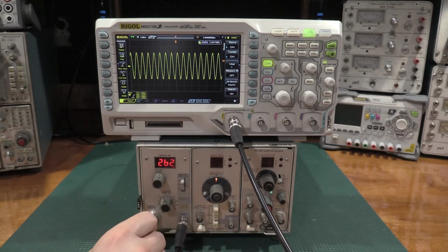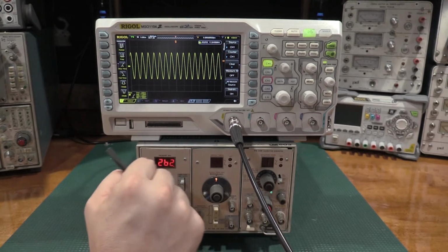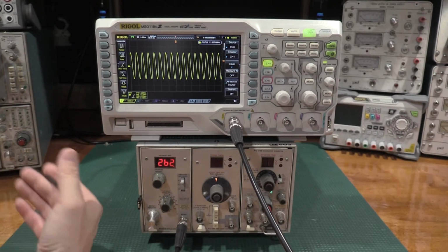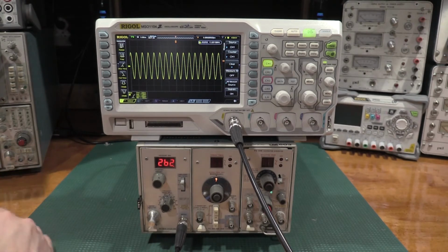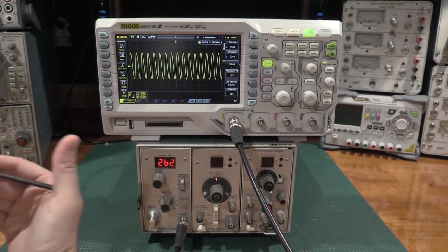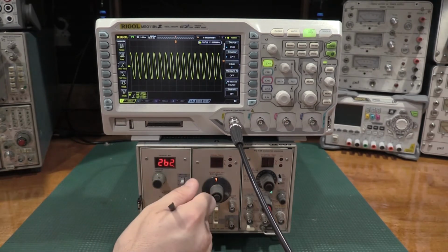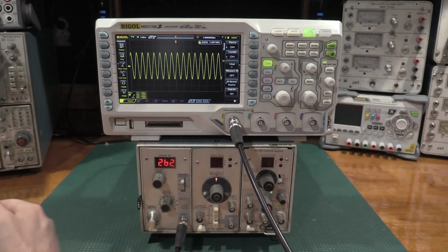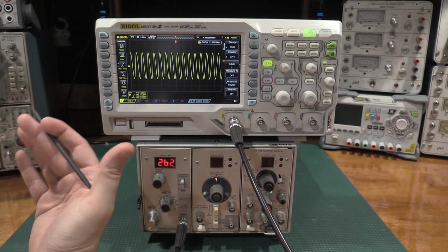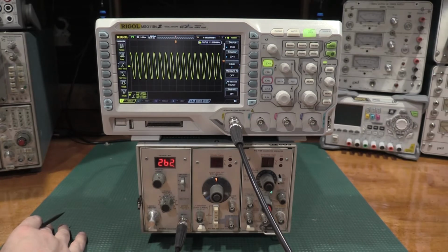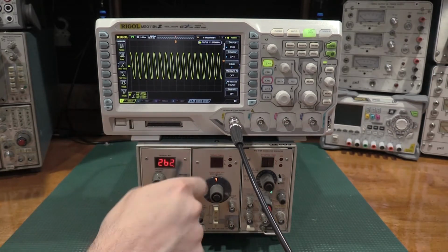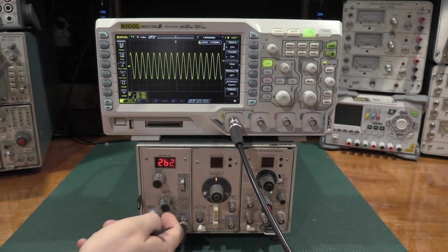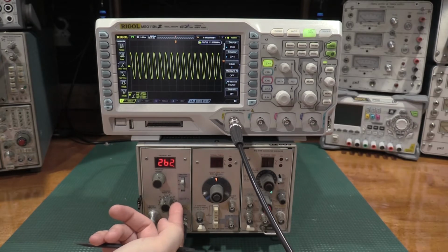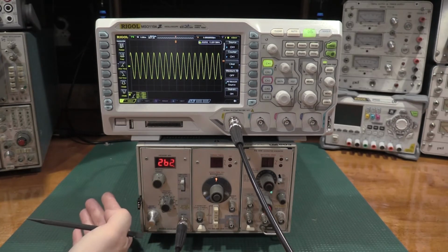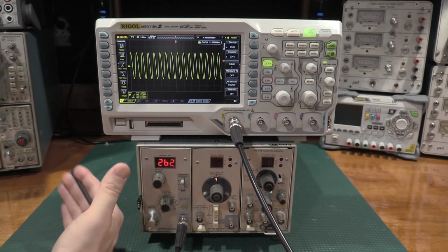But that's the thing, with it being a leveled sine wave generator, as you adjust the frequency, the amplitude doesn't change. So during a scope calibration, does that matter? For the most part, no. The only place that actually matters is when you're doing the bandwidth checks, and you need to know that this signal, the amplitude, doesn't change as you crank the frequency up. Anywhere it says sine wave generator to X divisions of display, you can use any sine wave generator for that as long as it hits the frequency response. I could use the SG501 for that at 50 kilohertz. It's when you have to do a frequency comparison where it says set it at 50, check it at 10 or 15. Now you need to have a leveled sine wave generator, and you need to be sure that the waveform or the amplitude isn't changing with respect to frequency.